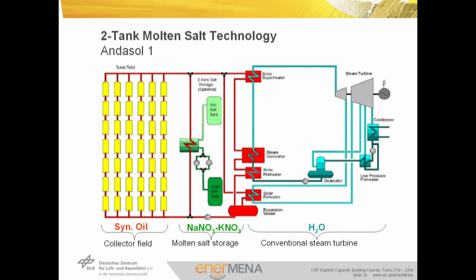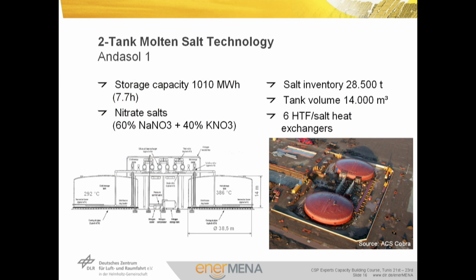An indirect molten salt storage system was first implemented at the Andasol power plants. Here, oil is used as HTF and energy is transferred to the salt via a heat exchanger during charging. During discharge, energy is transferred back from the molten salt to the thermal oil, which is then used to generate steam. The temperature difference between hot and cold tank is about 90°C, so the mass-specific storage capacity is about one-third of the SOLAR2 system.